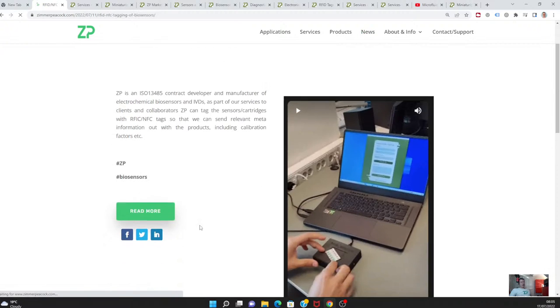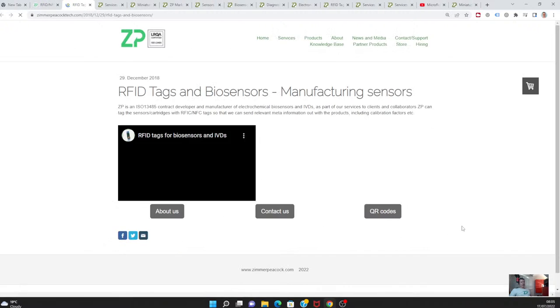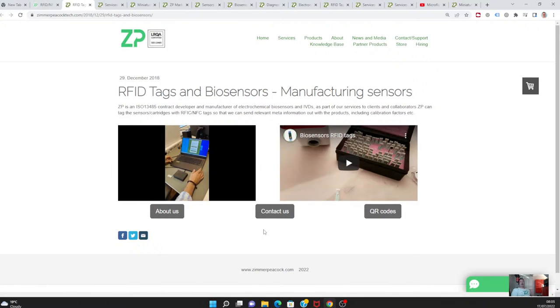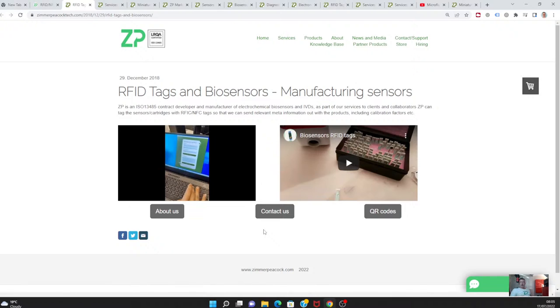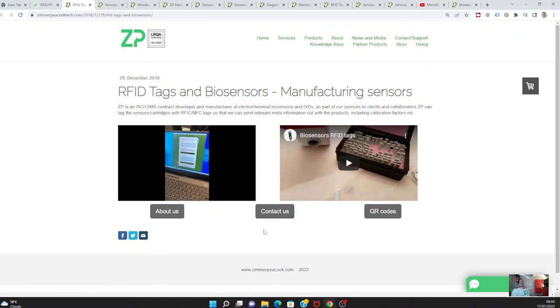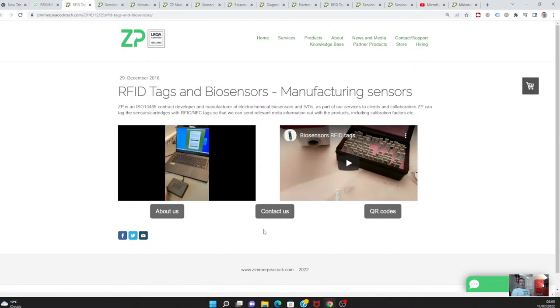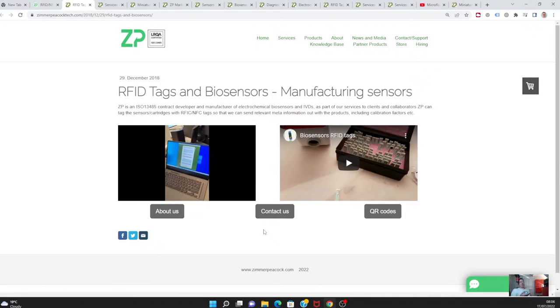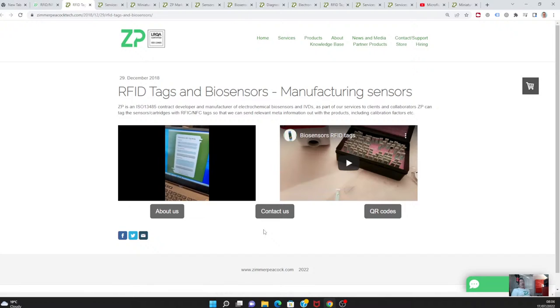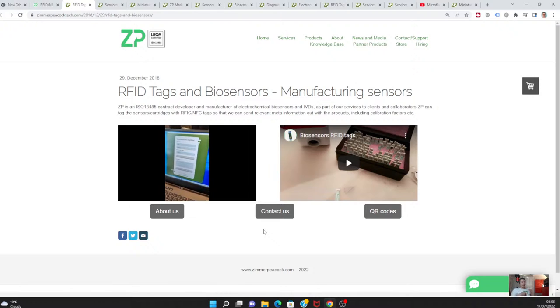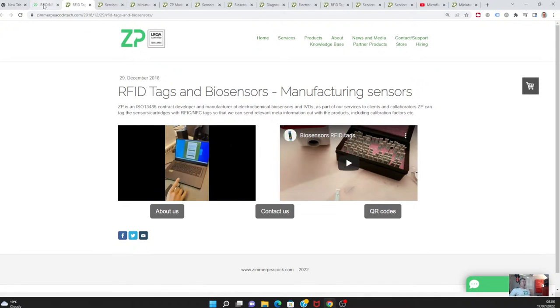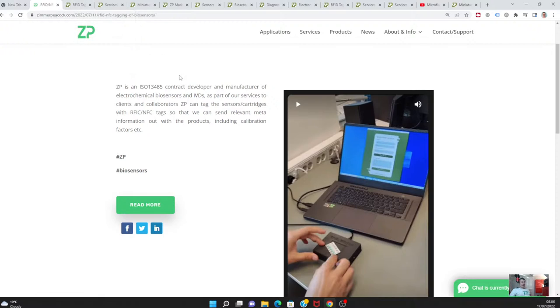Another important part of being a biosensor company is whenever you make a batch of biosensors, there will be things like sensitivity and offset, and from batch to batch you can end up with sensitivity and offset that's potentially variable. That's just inherent in manufacturing, especially when you're manufacturing something quite complicated. I love the fact that when you look at a biosensor it looks very simple, but there's a substrate, you print materials on that substrate, you functionalize these substrates with enzymes and antibodies—these could be several layers—and then you could put microfluidics onto these substrates. So at the end of it, you can have a batch of sensors that look just like the last batch but in fact there's been some subtle changes and the calibration factors have changed.